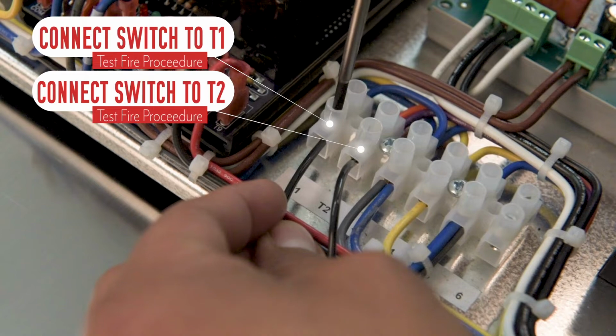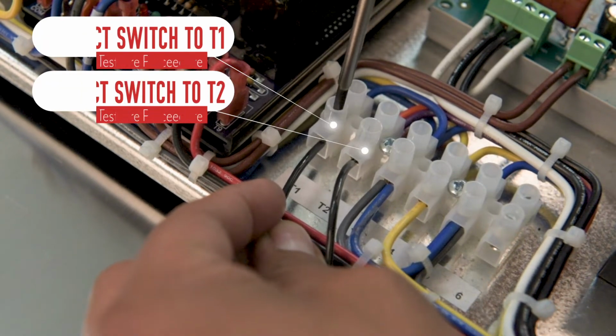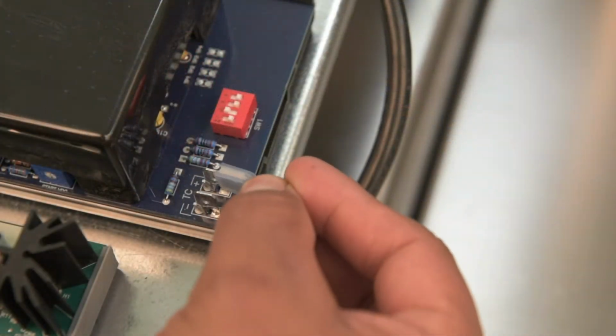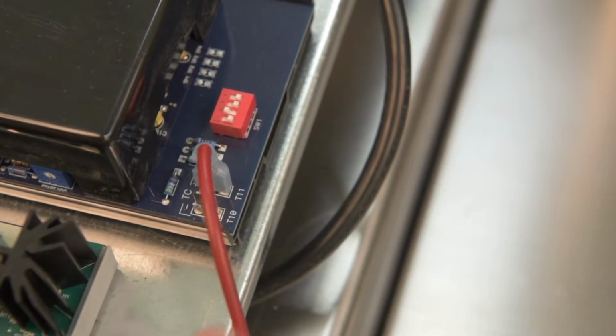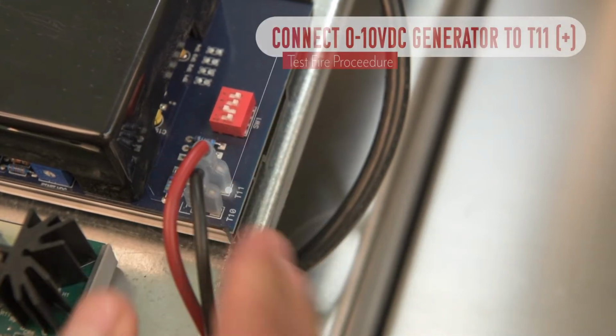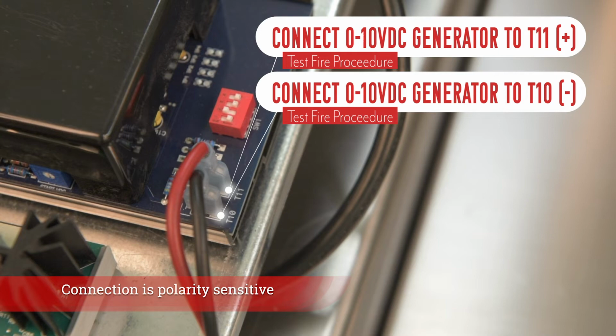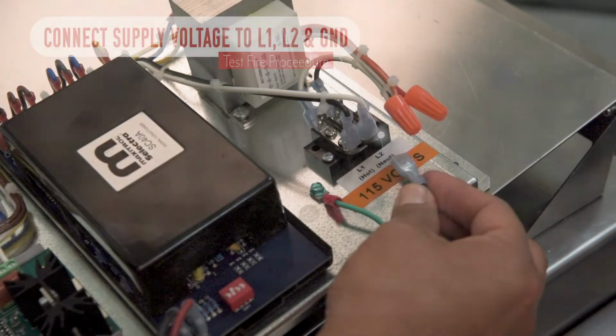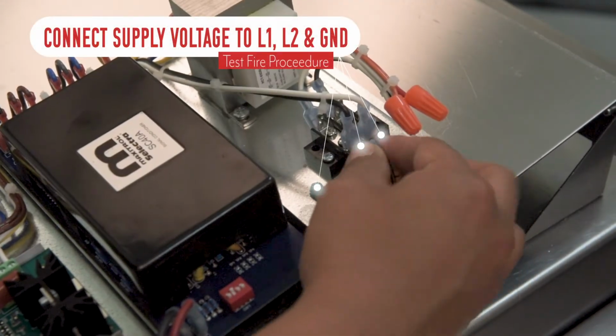connect the heat enable switch between terminals T1 and T2, connect the 0 to 10 volt DC generator to the SC40 signal conditioner input terminals T10 and T11. Make sure that the polarity is correct. In the field, you may control the heating unit with the air handler control. Be sure to follow the same testing procedure and modulating control signal values. Connect the supply voltages to L1 and L2 and ground terminals.